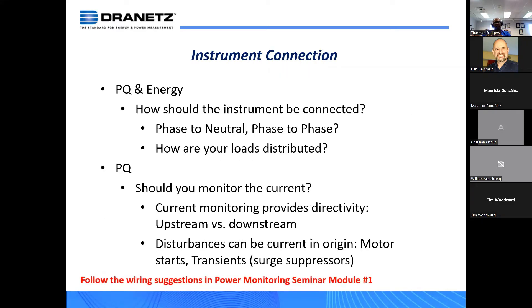Instrument connections: should the instrument be connected phase-to-neutral or phase-to-phase? It really comes down to how your loads are distributed. Usually in most PQ applications, phase-to-neutral is going to reveal more information. Particularly when it comes to harmonics, you want to look for triplens — the zero-sequencing harmonics that don't cancel out. They add in the neutral, so depending on the nonlinear loads causing those zero-sequencing harmonics, they add in the neutral, and the presence of a neutral gives you the most results in a PQ application.